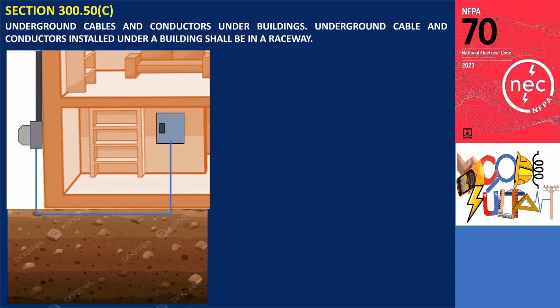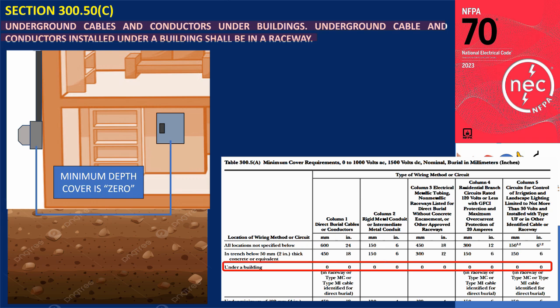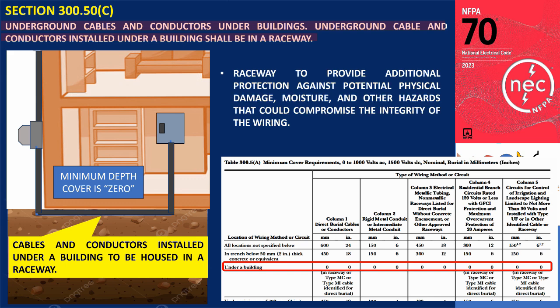Section 300.50(C): Underground cable and conductors installed under a building shall be in a raceway. Since Table 300.5(A) cover under the building is zero, the code requires all underground cables and conductors installed under a building to be housed in a raceway. This requirement is in place to provide additional protection against potential physical damage, moisture, and other hazards that could compromise the integrity of the wiring.